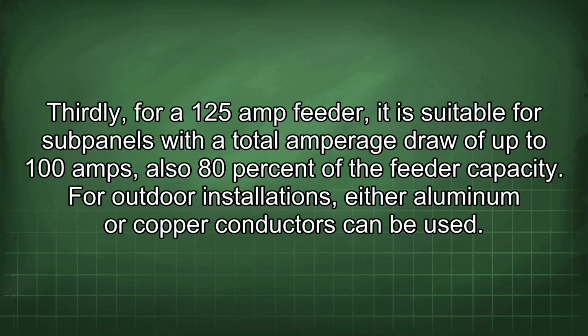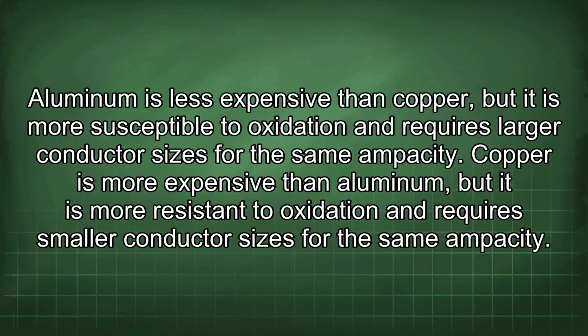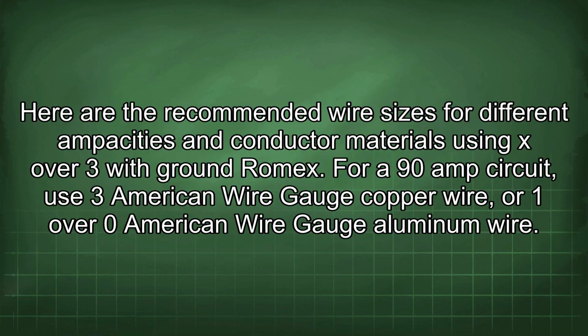For outdoor installations, either aluminum or copper conductors can be used. Aluminum is less expensive than copper, but it is more susceptible to oxidation and requires larger conductor sizes for the same ampacity. Copper is more expensive than aluminum, but it is more resistant to oxidation and requires smaller conductor sizes for the same ampacity.